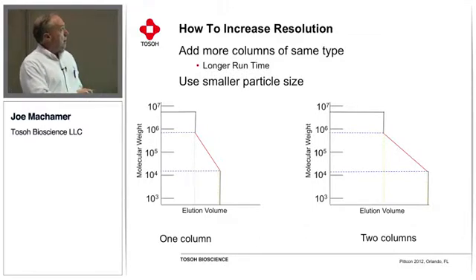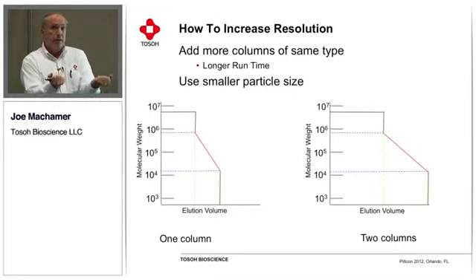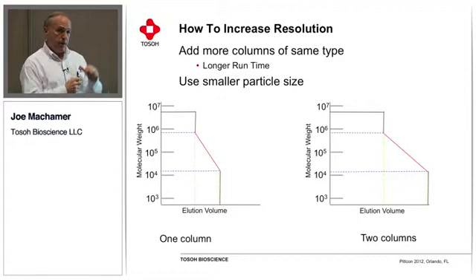So what you can do if you want to increase the resolution, of course, there's a couple of things that are done. Typically you could add more columns of the same type. So take two columns that have identical material in them, hook them together, you're increasing the amount of pore volume in the column, and you increase the resolution. Or the other thing one can do, of course, is to use a smaller particle size in the column.